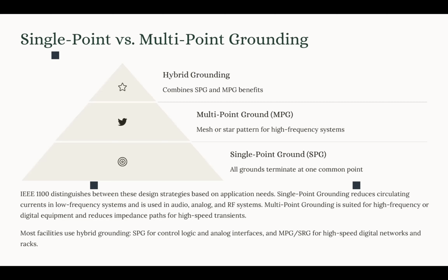Normally, we use that in low frequency, high sensitivity analog systems, like audio and recording studios, or medical imaging, or low frequency RF systems. And this SPG has some pros and cons. One of the pros is that in a low frequency system, it controls the circulating current. So it eliminates the ground loop because there is no loop actually. All the systems are directly connected to a bus bar, to the building's ground. It also provides a single defined reference potential, so minimizing the analog measurement error.